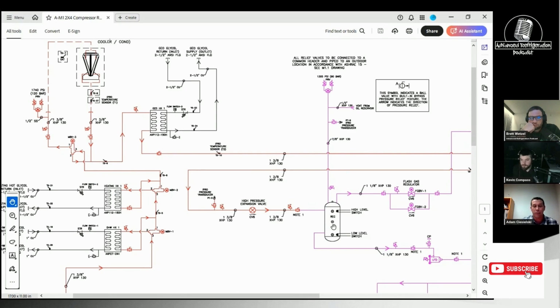So you can get more heat out of it, because you're wasting refrigeration load basically only on the flash gas bypass. You're basically adding more load to the medium temp compressors, which essentially is adding more heat of compression energy for more heat reclaim, right? That's correct. Okay.